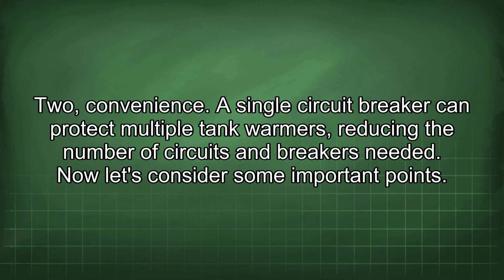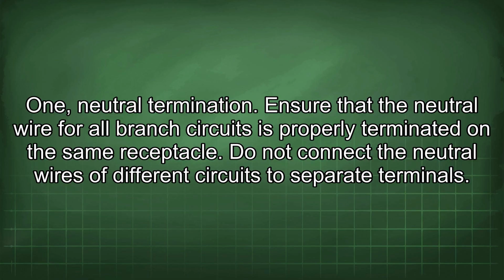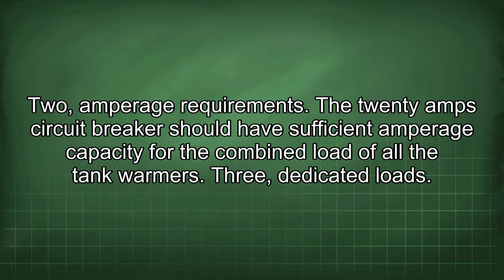Now let's consider some important points. 1. Neutral termination. Ensure that the neutral wire for all branch circuits is properly terminated on the same receptacle. Do not connect the neutral wires of different circuits to separate terminals. 2. Amperage requirements. The 20 amp circuit breaker should have sufficient amperage capacity for the combined load of all the tank warmers. 3. Dedicated loads.